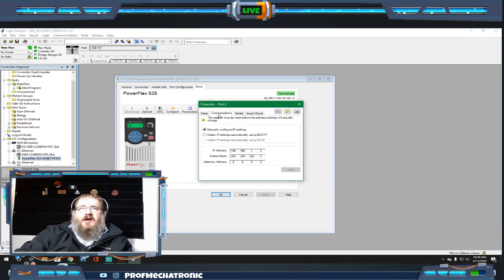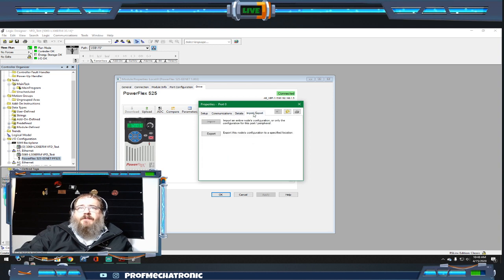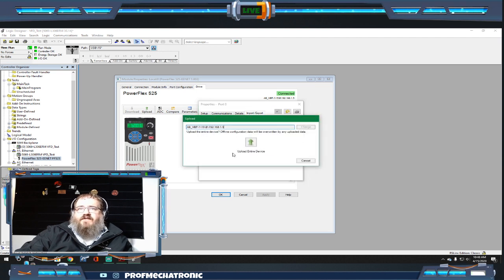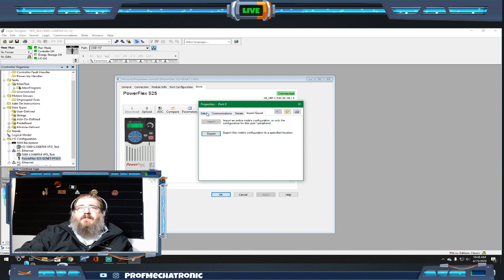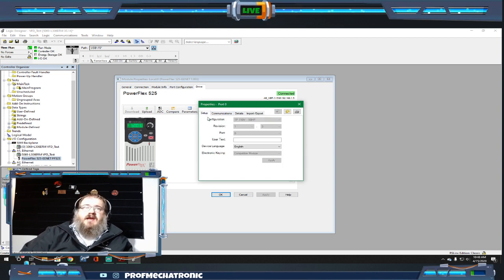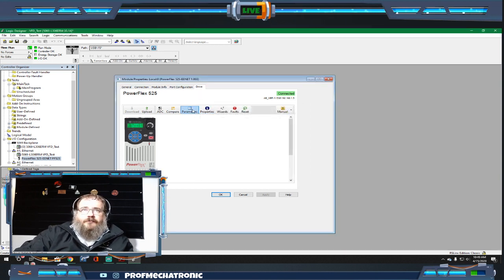Parameters is very straightforward. This is where we have our communications, some simple import/exports. You can export everything if you want to save the data — export this node's specific information and save it as a backup, which is always good, especially in the maintenance field. In skilled trades, we always want to keep backups in case things fail. There's nothing worse than having a motor fail at 1 o'clock in the morning and having to manually rewrite all of the data because somebody didn't do a backup properly.